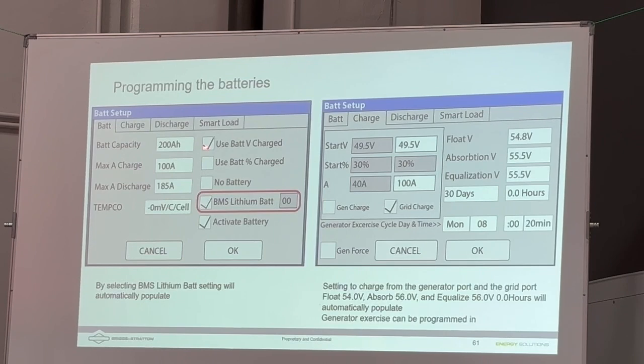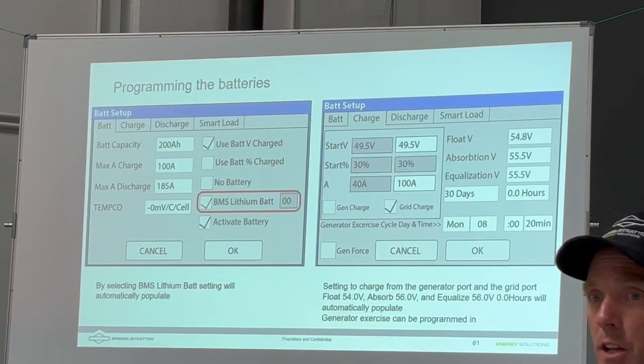If you check battery voltage here, it will display all your values and your set points in terms of voltage of the battery. You can only check voltage or percent. If you use percent, then it will display all the values as the percentage state of charge. So for instance, 51.2 is the voltage at which this battery is half charged, at a 50% state of charge.